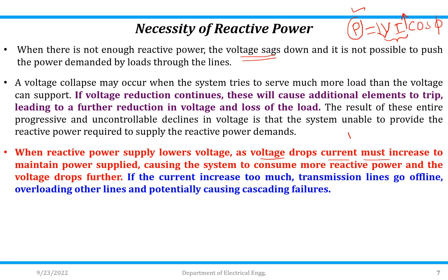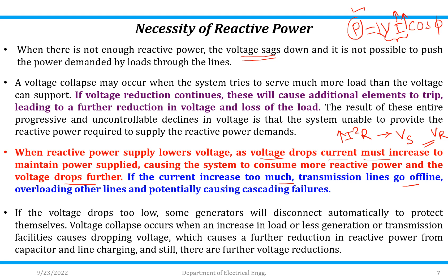Since losses are denoted by I²R, if current increases then losses also increase. As losses increase, there will be a difference between the sending-end voltage and the receiving-end voltage, further leading to voltage drop. If the current increase is too much, transmission lines go offline, overloading other lines and potentially causing cascading failure. Some generators will disconnect automatically to protect themselves if the voltage drop is too low. Voltage collapse occurs when an increase in load or less generation or transmission capacity causes dropping voltage, which causes further reduction in reactive power from capacitors and line charging, resulting in still further voltage reductions.